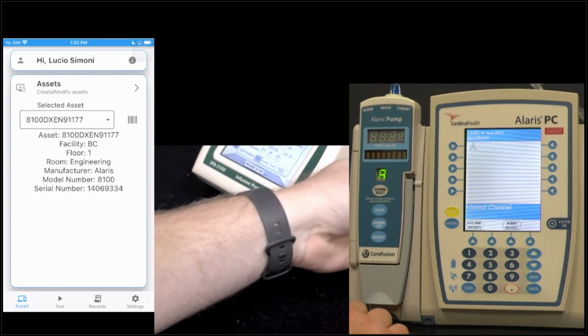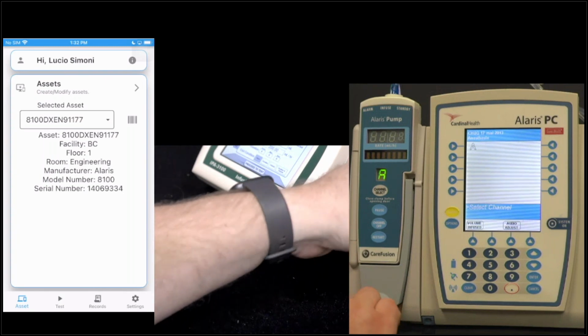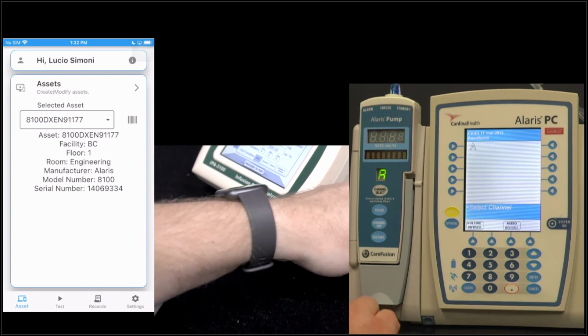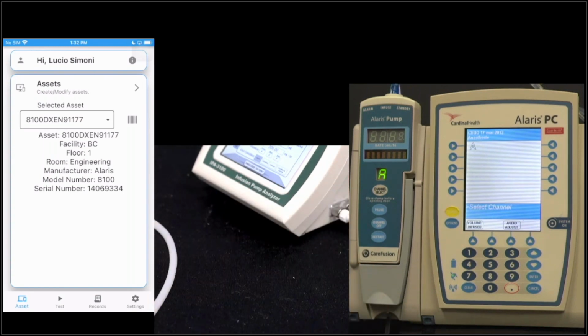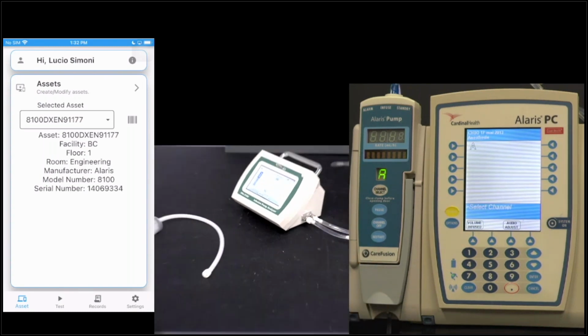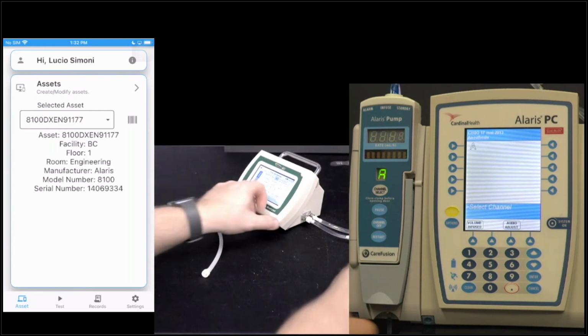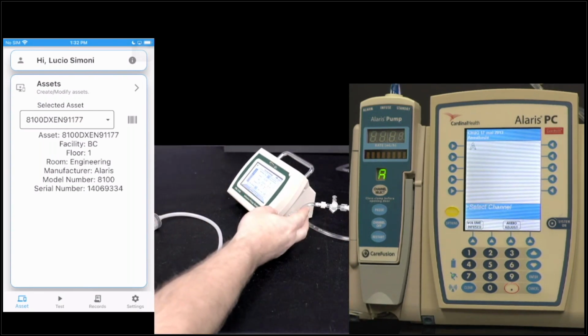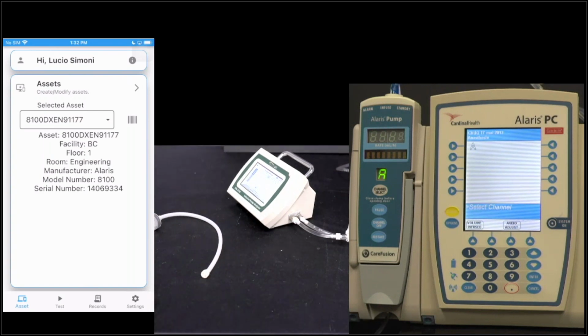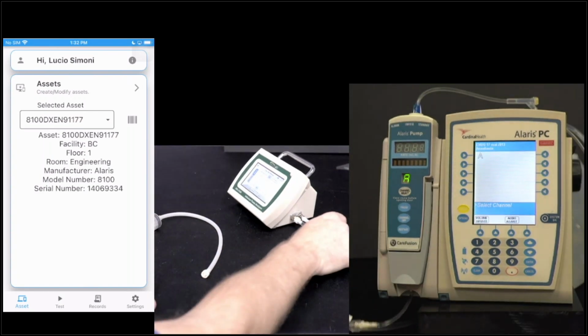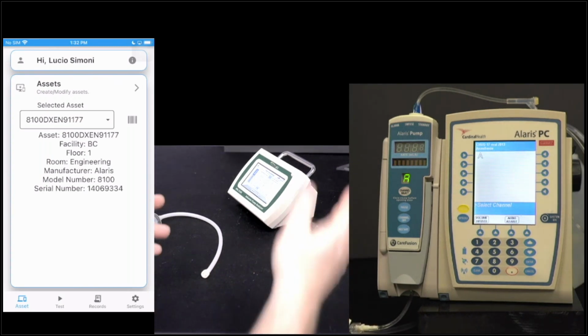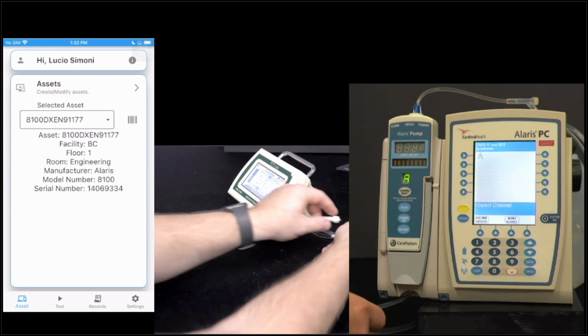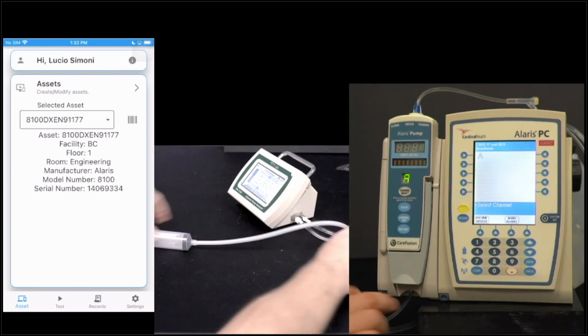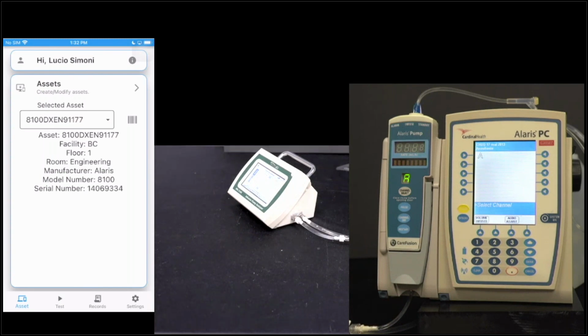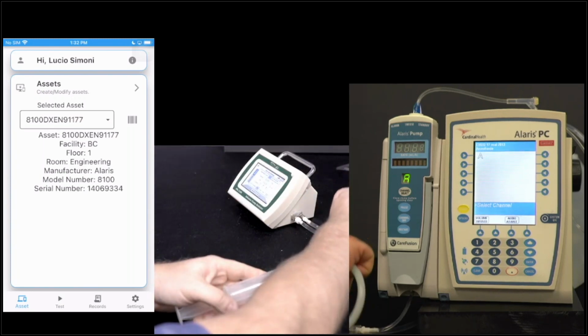So I'm going to put in a T. I apologize for the camera floating around here. I'm going to zoom out a little bit so we can see what's going on. So I've got a T in the line after the infusion pump. Here's my T. I can't see exactly what's in the middle, but anyway, I'm going to hook up a syringe. I'm going to force a bubble into the test, and we'll see that bubble flow down into the 3100, and we'll see what happens during that test.